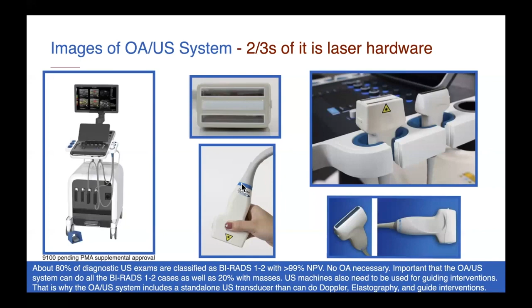This is a larger view of the probe. The 18 megahertz transducer in the center has a very wide bandwidth because the frequencies at which we detect the OA signal are quite low. So it goes all the way from 1 megahertz to 18 megahertz. The standalone ultrasound probe is 5 megahertz to 18 megahertz. It's 50 millimeters wide, and we can fire anywhere from 35 to 55 frames a second on ultrasound, but we can only fire 10 laser signals per second of OA, and it takes both a long and a short wave to create a frame. So that means that the color frames are updated 5 frames per second.